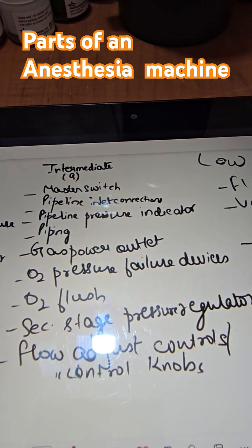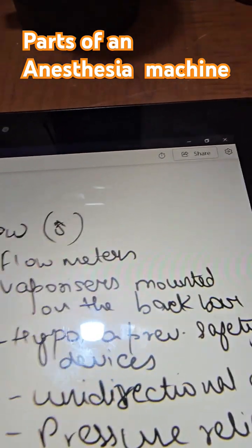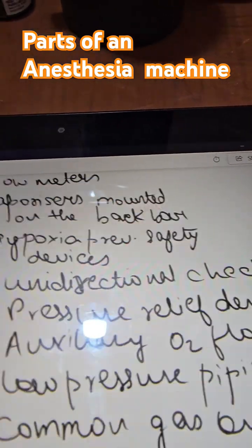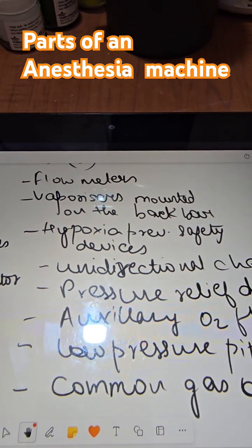The intermediate pressure system also includes the oxygen flush, second stage pressure regulator, and flow adjust controls or flow control knobs.